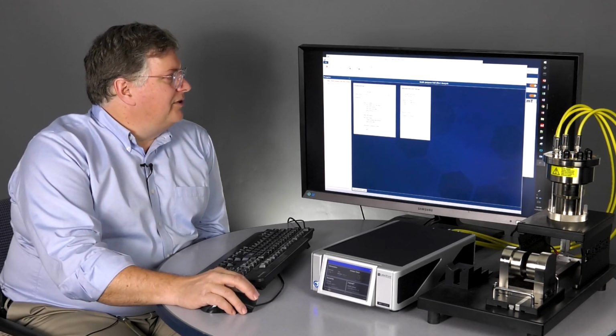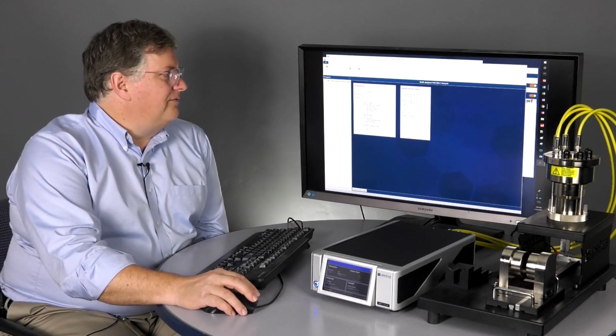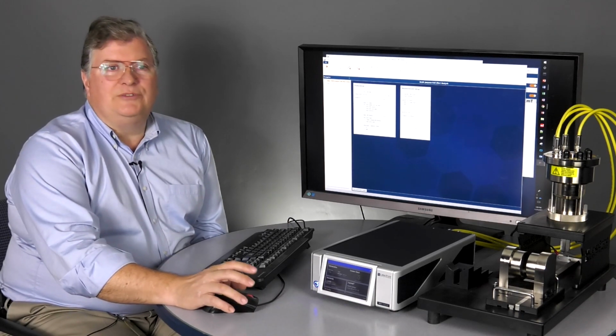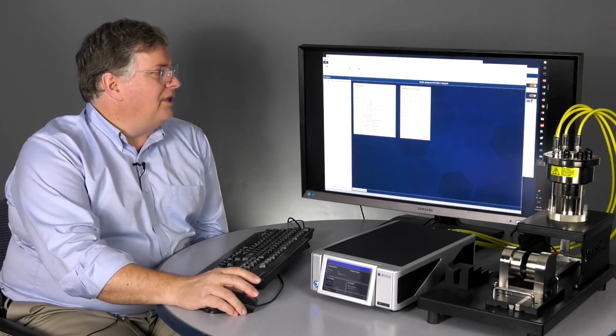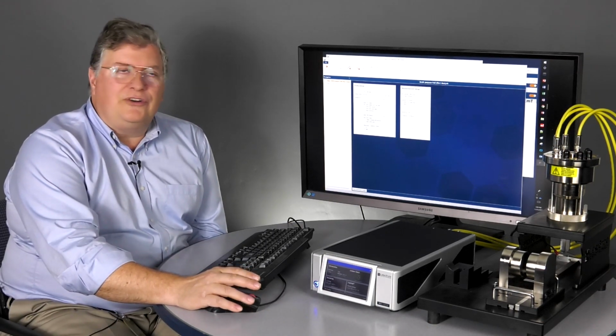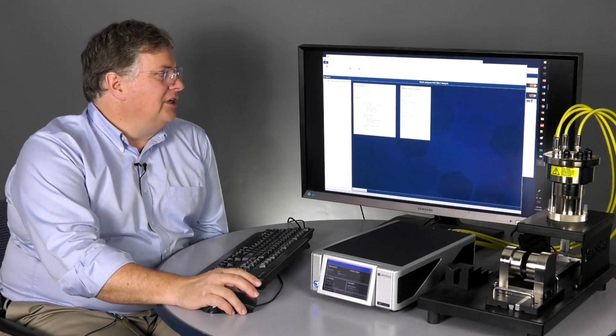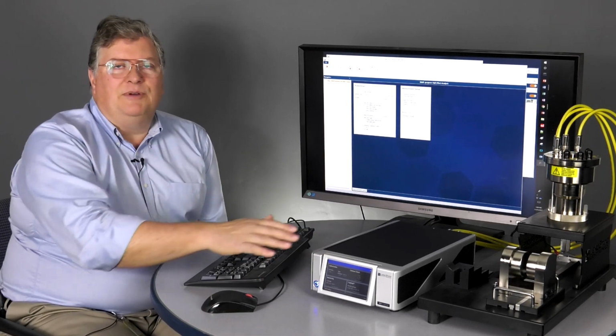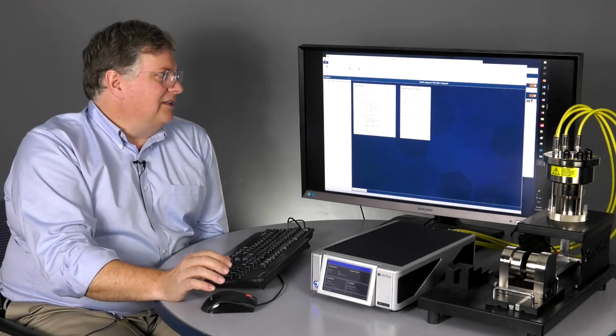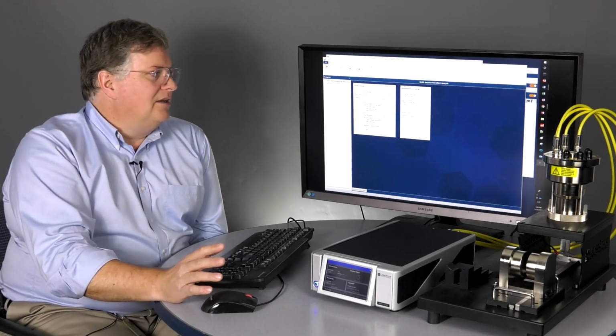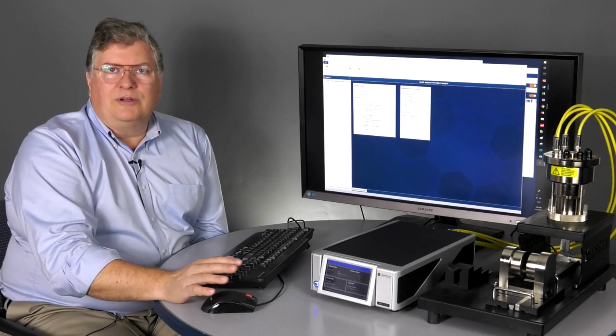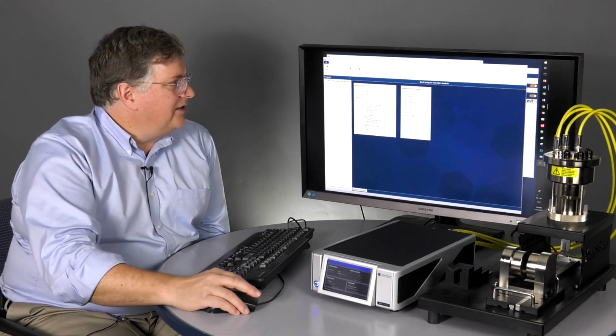Now, these other parameters I'll leave alone. These are defaults for the blanking time, basically a settling time after the switches are arranged, and a compliance voltage. So here in standard resistance, we are sourcing current. So our compliance voltage is only a 10 volt maximum with the M91. That's appropriate for most things, not a concern. But if you do have a lower compliance voltage that you want, you can specify it there.